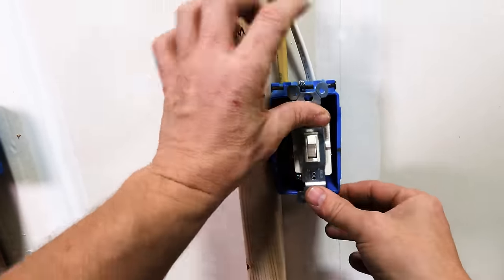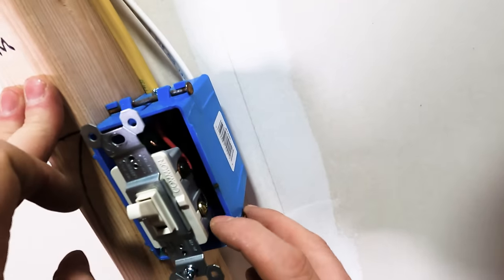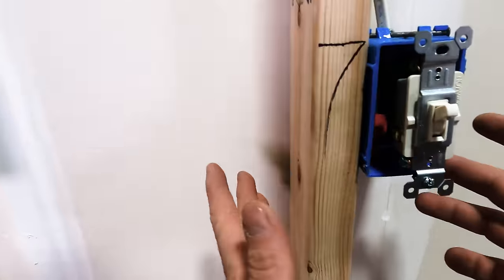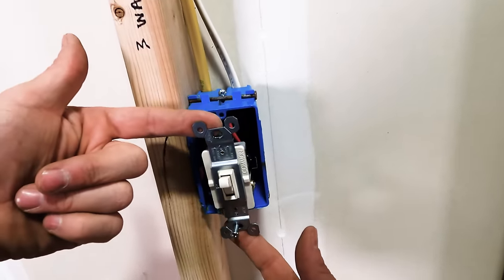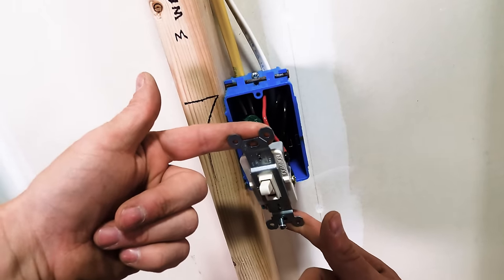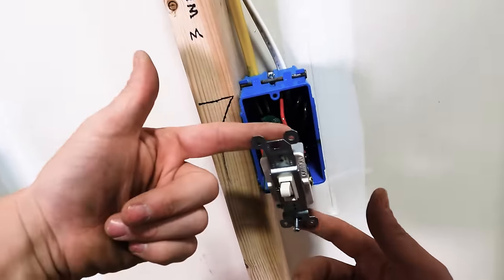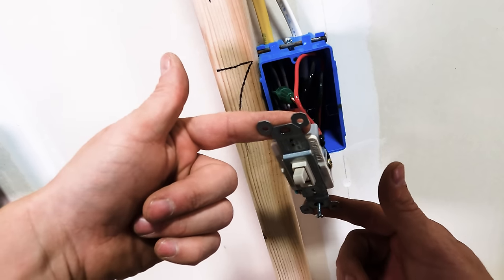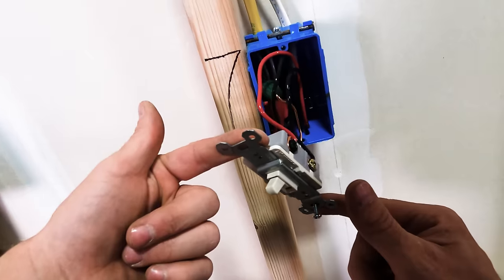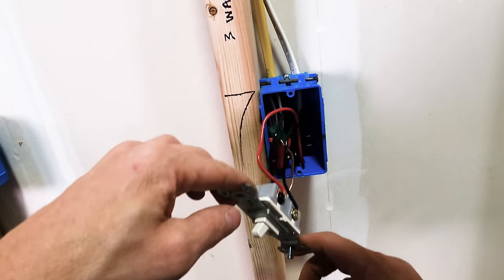Anytime that you take a device out, you don't want to just rip the thing out. You want to look at it first and be like, okay, well, I know there's nothing going weird. There's nothing loose because sometimes loose terminations make things happen as well. And then you slowly, when you're troubleshooting, always very slowly pull everything out. It's not because you're going to get shocked, you could I guess, but you don't want to change the state of whatever's happening. So you always want to look around very slowly, take everything out. And once you realize, okay, me messing with this device is not going to change the problem or change the state of the problem and now I'm chasing a ghost, then I pull the whole thing out.